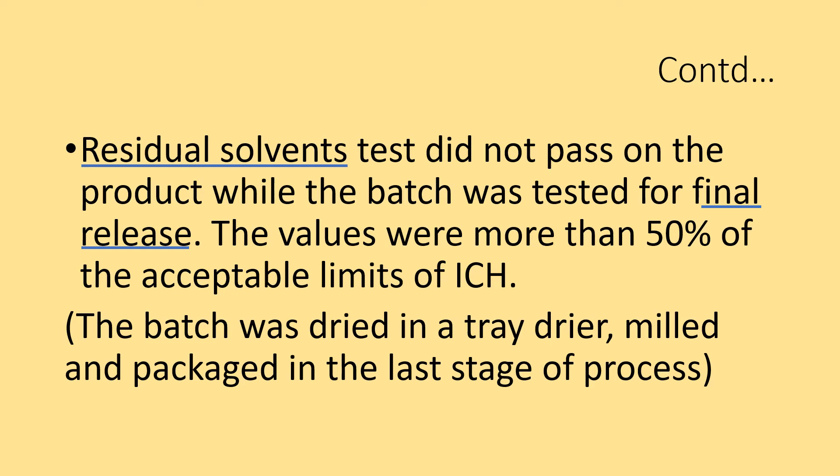Initially, the laboratory OOS investigation should include checking the validity of the standards, preparation of standards including the weights taken for the standards, glassware used, and compliance to system suitability parameters. Since the residual solvents are being analyzed using a headspace analyzer, the investigation should focus on potential leaks in the headspace system. All these parameters have to be checked and documented with details of exactly what the observations were.